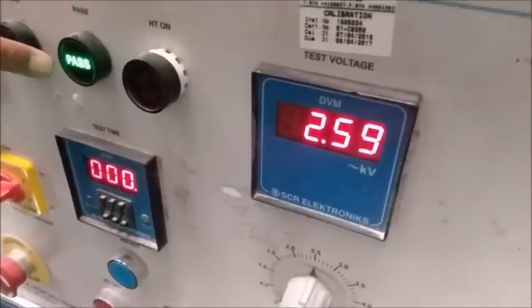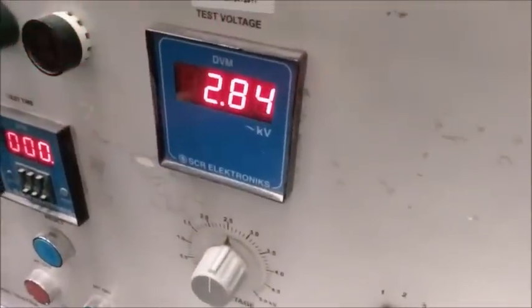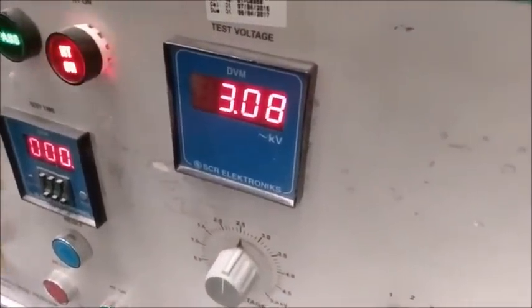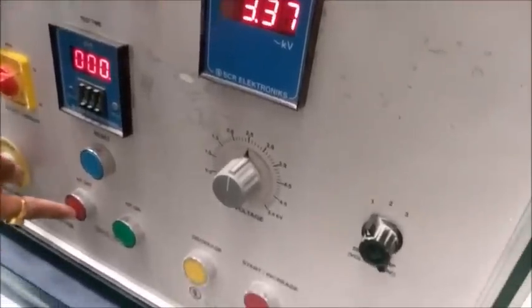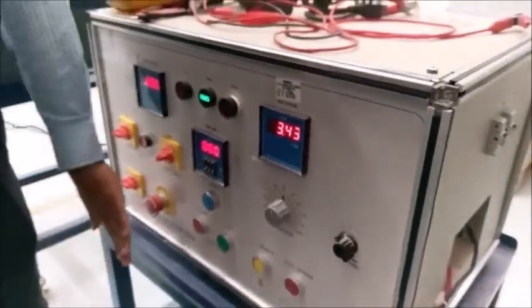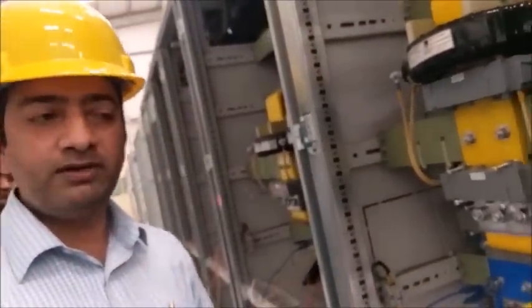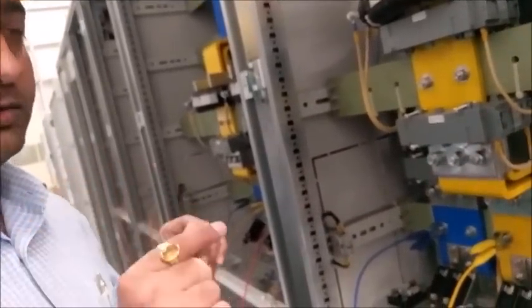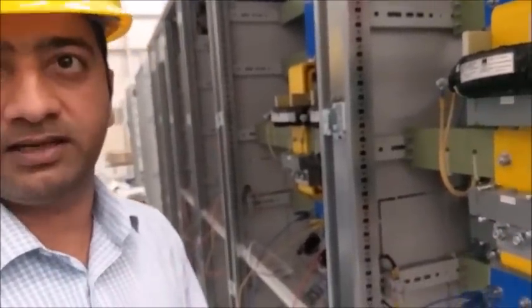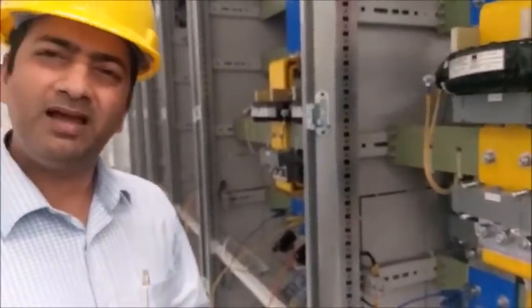See, now it has passed and the voltage starts to lower. Actually, it was in manual mode, and one more thing, there is an emergency stop. Once the supply is off, it is not problematic. Only one thing we have to take care of always, in DC mode or AC mode: whenever the supply is hot, meaning actual testing mode, you should not touch anything. But after this you can touch, no problem.